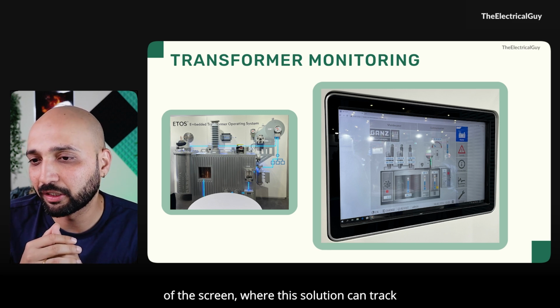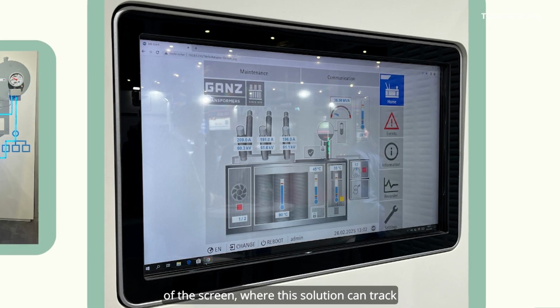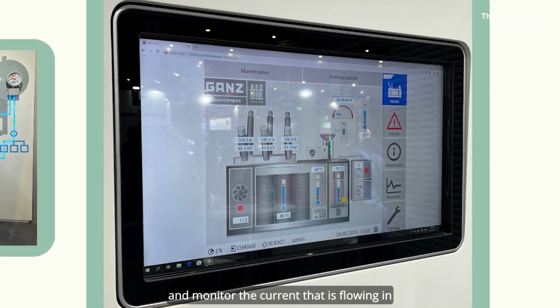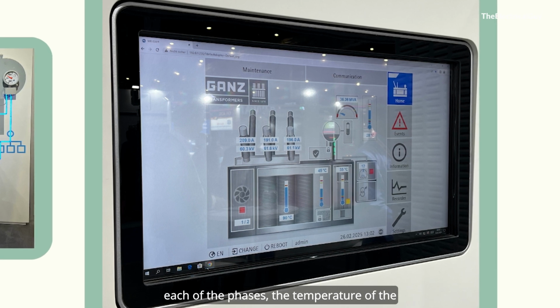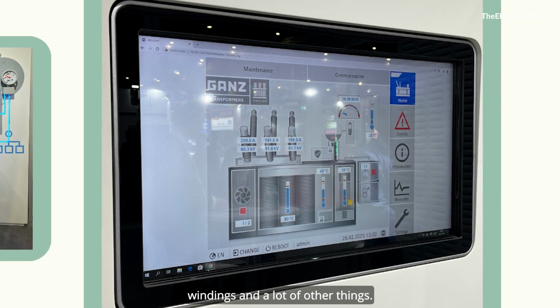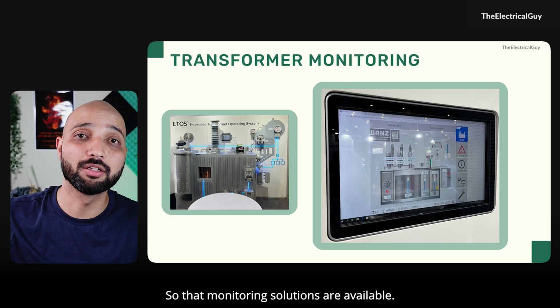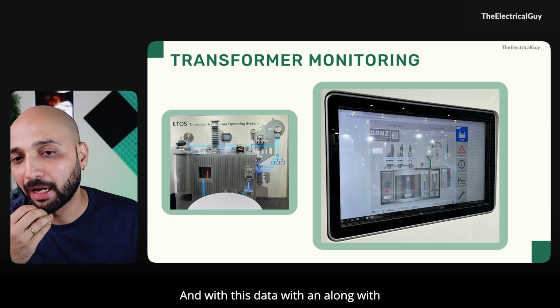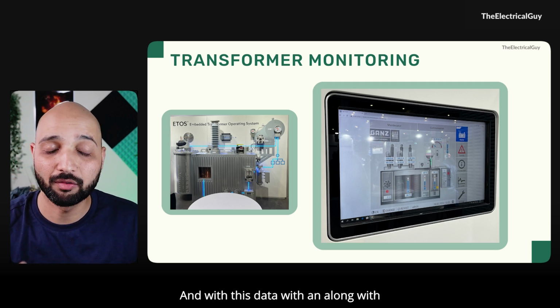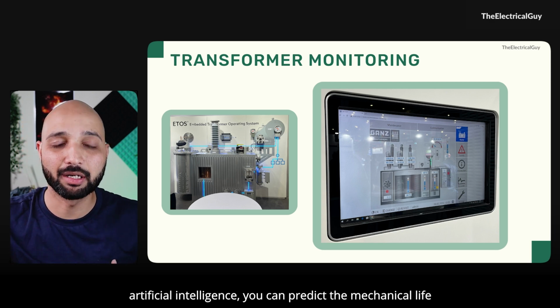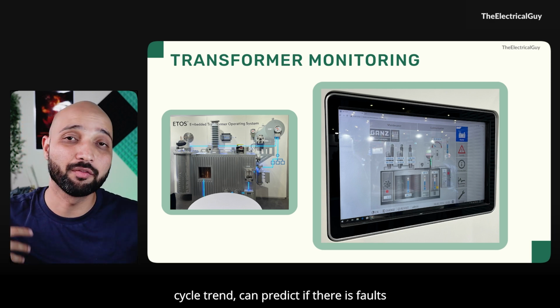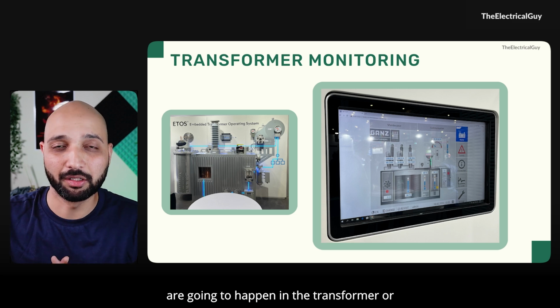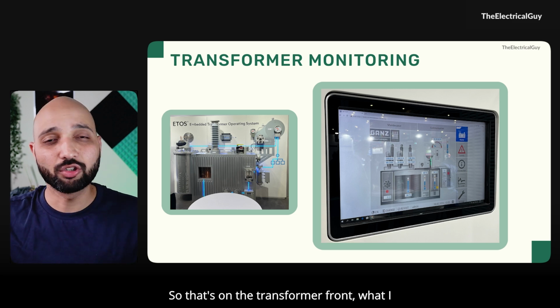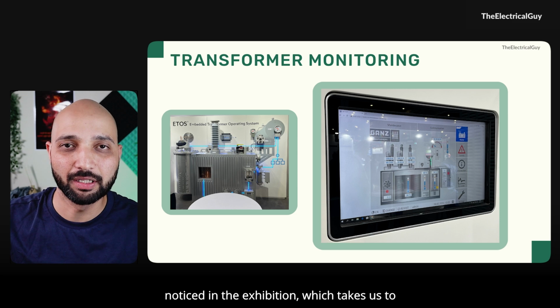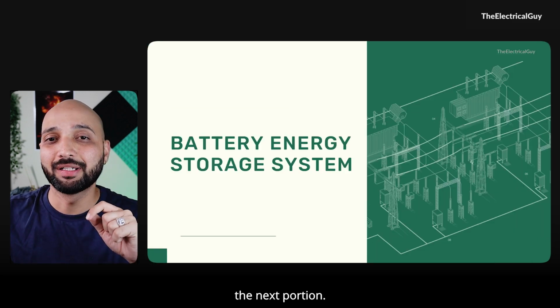You can see on the right-hand side of the screen how this solution can track and monitor the current flowing in each bushing, the voltage rating of each phase, the temperature of the windings, and other things. With this data, along with artificial intelligence, you can predict the mechanical life cycle trend and whether faults are going to happen in the transformer. That's what I noticed on the transformer front in the exhibition.